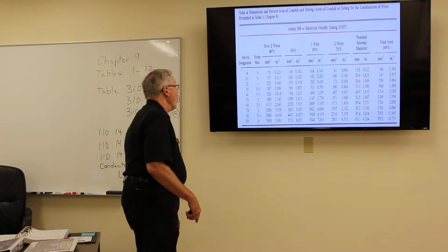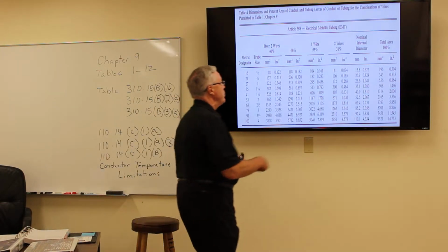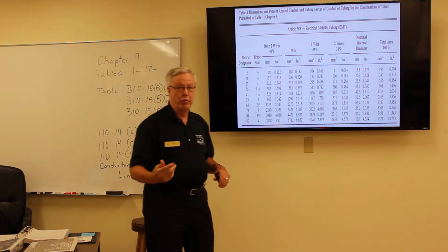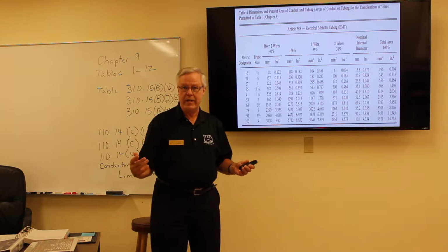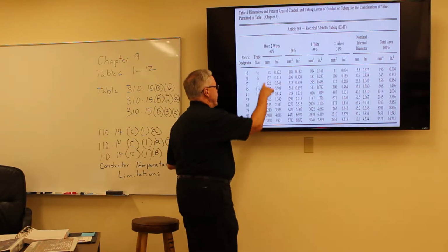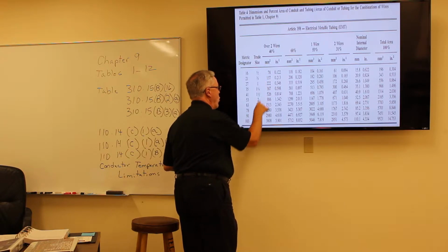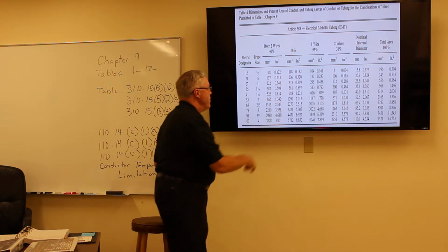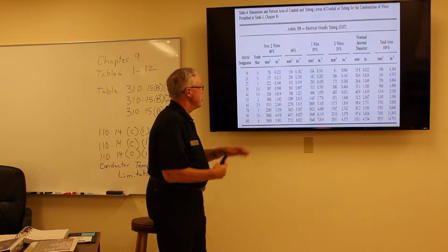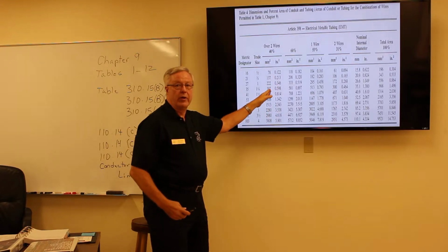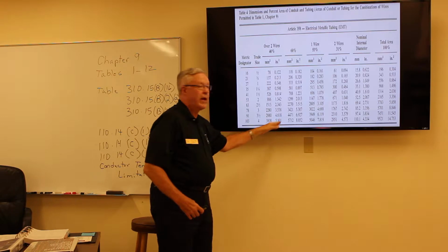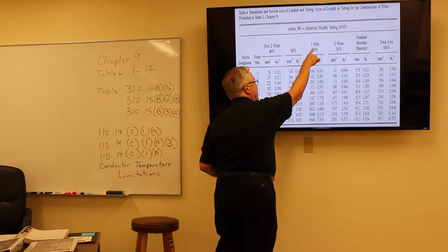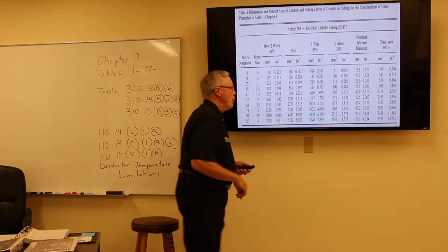If you go to table 4, you'll notice in each one of the tables, it is listed by the type of raceway system used in chapter 3. In here, we'll be dealing with EMT in this situation. You notice the trade sizes, 1/2 inch, 3/4, up to 4 inch, and over 2 wires, 40%. This is the dimensions inside the raceway that those conductors will fill, and so we have to make sure that when you do the calculations, the raceways do not exceed the fill of the conduit. There's your 53% for 1, and your 2 wire for 31%.